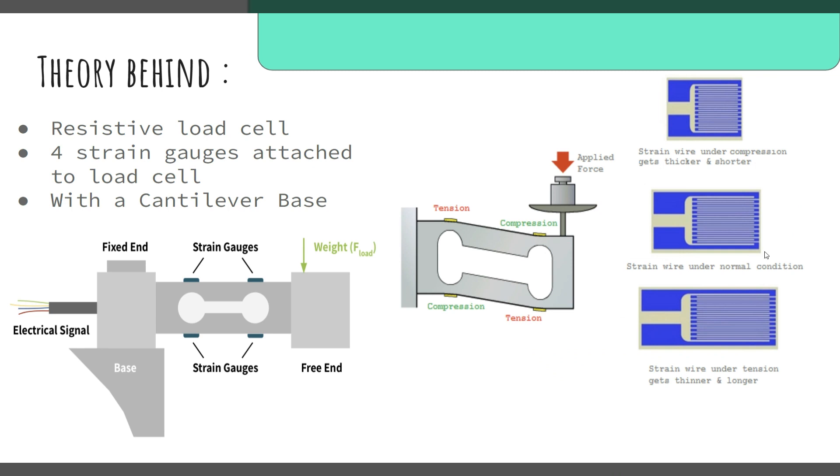When we apply force onto the cantilever base or weights under the cantilever base, there are compression and tensions created in the strain gauges attached here on our beam of load cell. Because of this tension and compression, there is a change in the length of the wire, so the area of cross section varies. Since resistance is inversely proportional to area of cross section, the resistance changes in both cases.